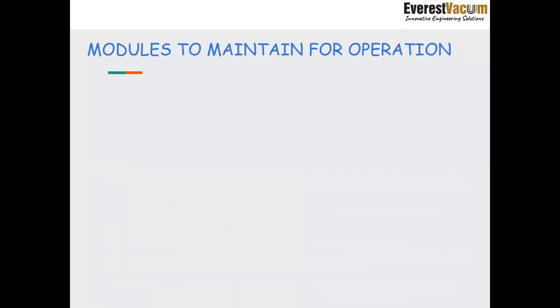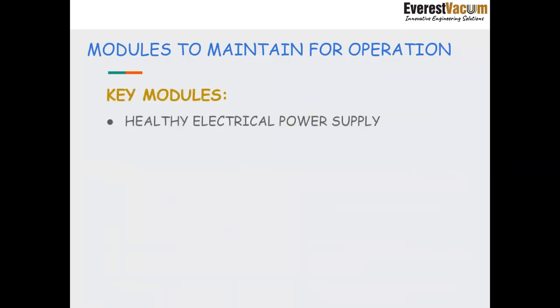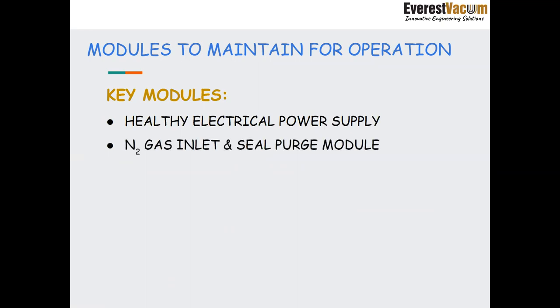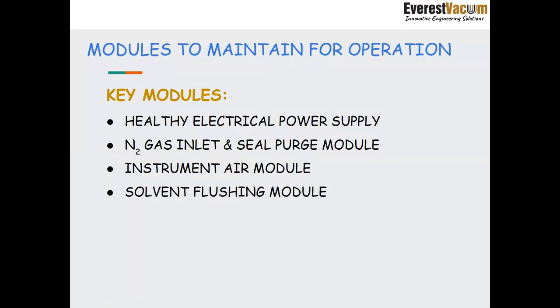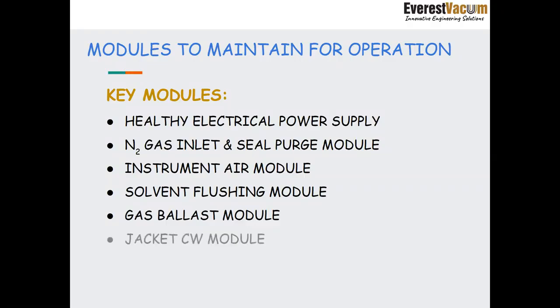So what are all the modules that we need to maintain for the operation? The key modules include a healthy electrical power supply. It should have a healthy 3-phase power supply. And then nitrogen needs to be available. There are 2 modules, inlet and seal purge modules. Instrument air for the butterfly valves or any other electropneumatic valves available in the system. Then there is solvent flushing to flush the pump of any contaminants. Gas ballast to run the pump hot and to avoid condensation inside the pump. And there is a cooling water jacket module to dissipate the heat as well. So all these modules need to be maintained for the system to function properly.